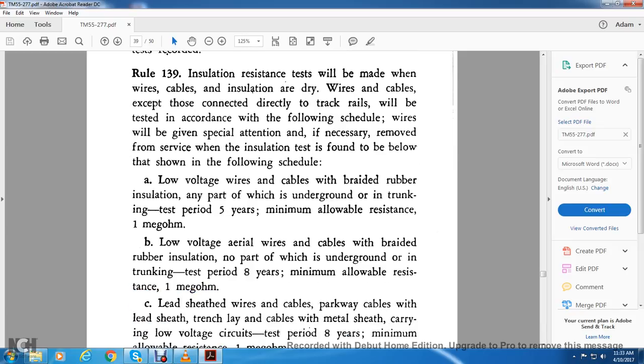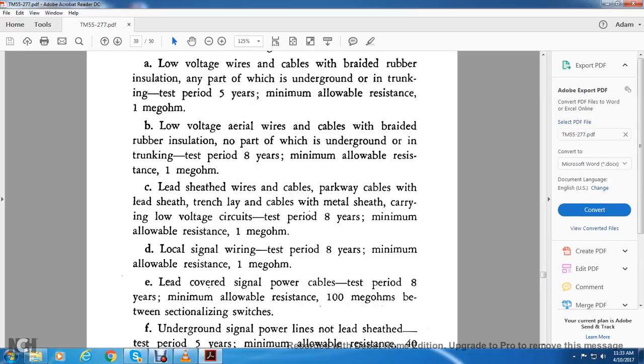A. Low voltage wire cable with braided rubber insulation, any part of which is underground or in trunking: test period 5 years, minimum allowable resistance 1 megohm. B. Low voltage aerial wire cables with braided rubber insulation, no part of which is underground or in trunking: test period 8 years, minimum allowable resistance 1 megohm.